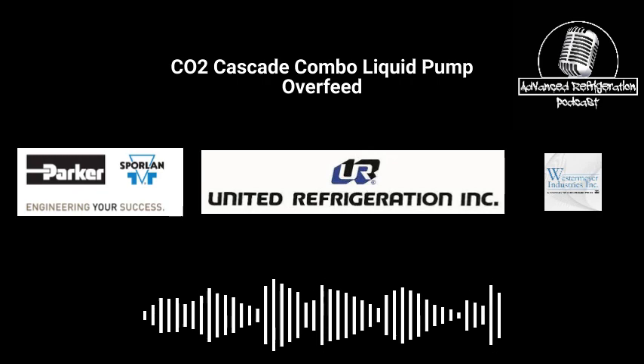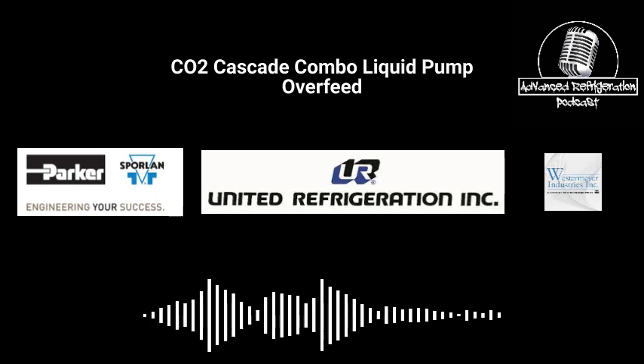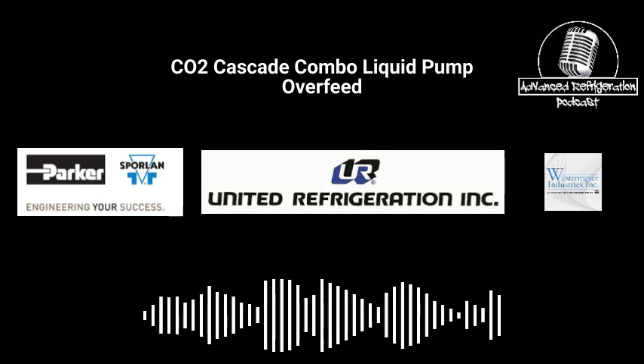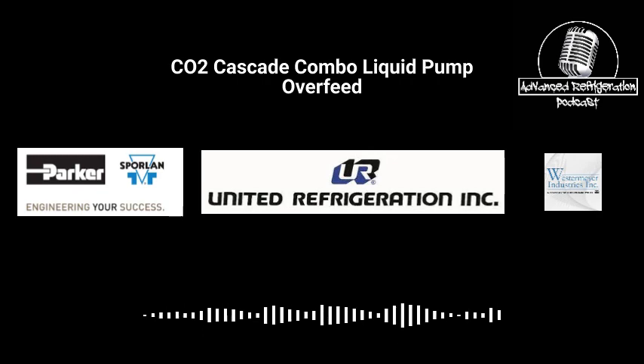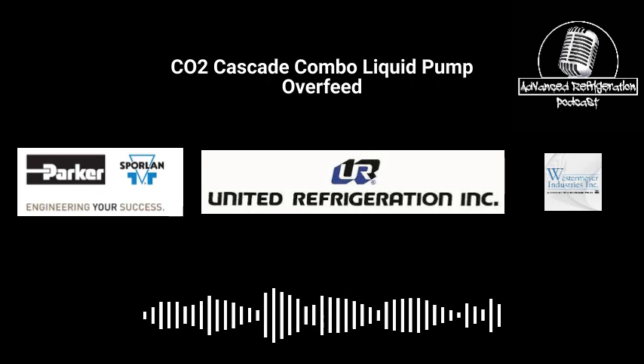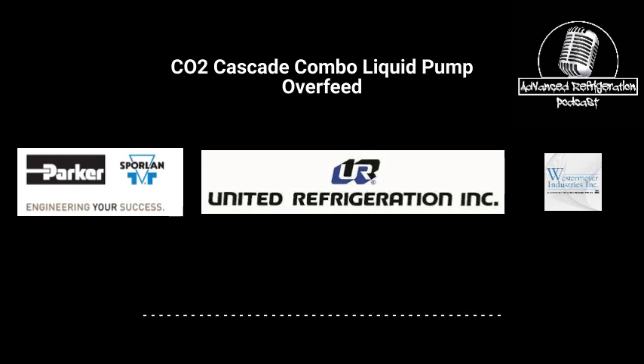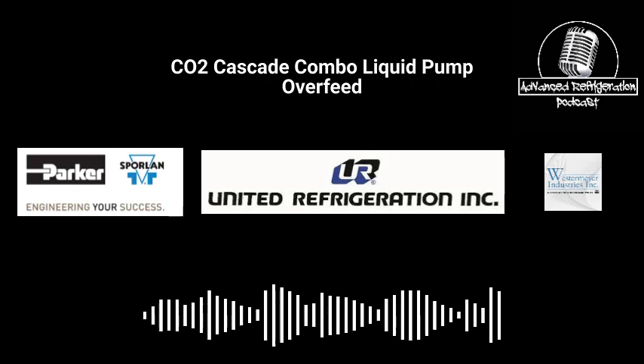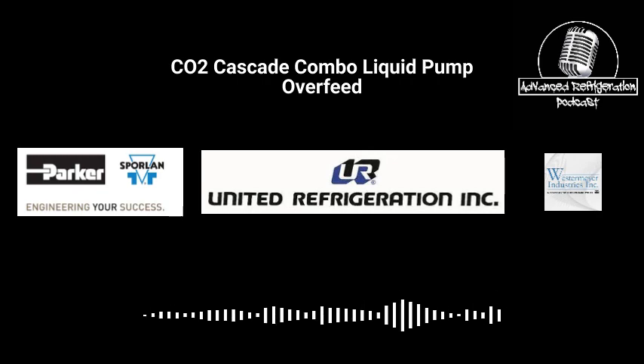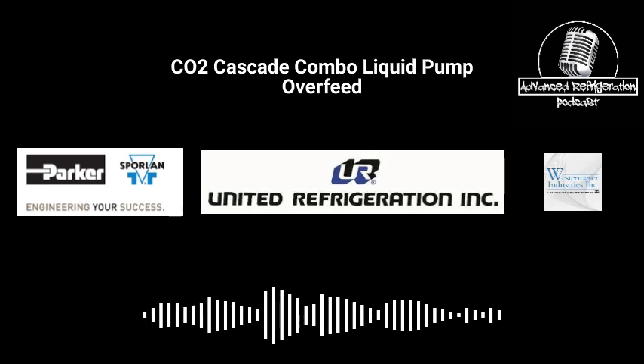I mean, you could probably charge that with a running level. Yeah. If everything was running and you had all the cases on, I'd imagine you could probably charge it to a running level. You should see a way steadier receiver level on that than you would on a normal thermal siphon, because you're going to have that compressor load on there. Your load's going to be a lot more constant, I would think, on that side of it. So you should have a more steady receiver level.